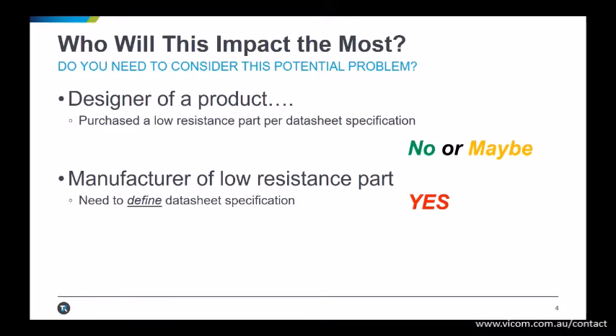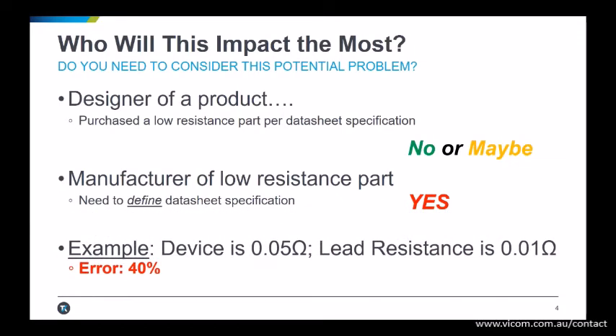Consider the situation where you are making 50 milliohm resistors and your test setup uses leads that are 10 milliohms each. This has the potential to result in 40% error in what you are measuring.